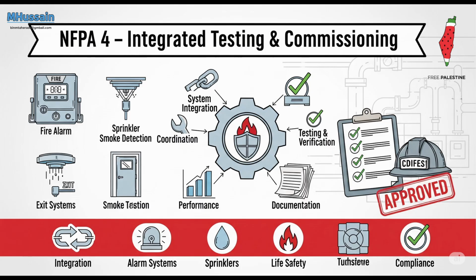It's about bringing older buildings up to speed. Okay, so initial, periodic. What's the third trigger? It's trigger-based testing. This means integrated testing is also required whenever certain events occur. Like what? Like when new fire protection or life safety systems are installed and connected into existing ones, or when existing systems are modified to become part of interconnected systems.